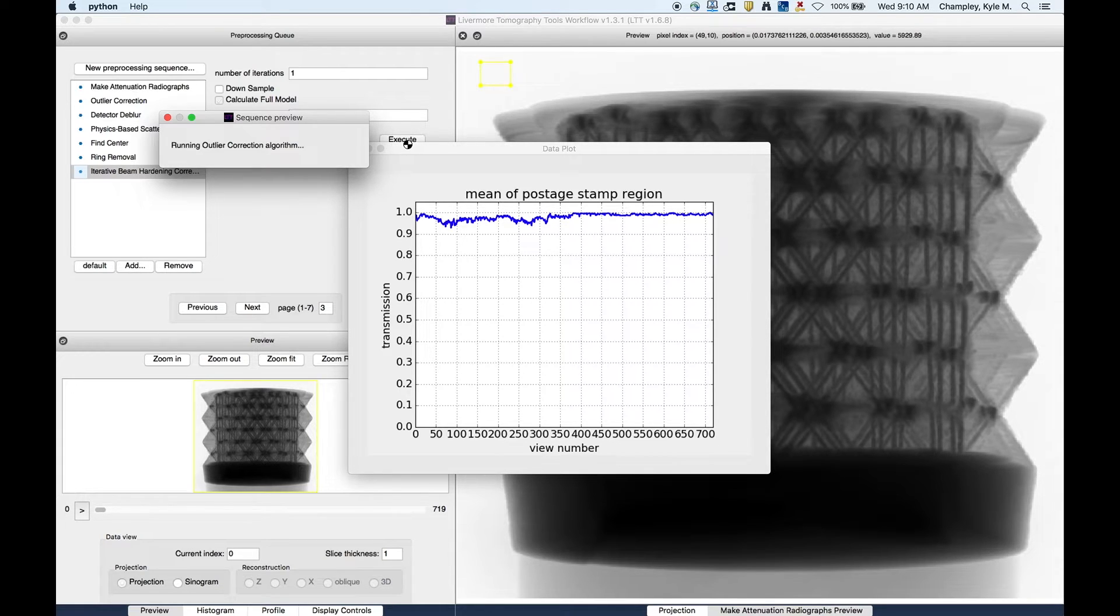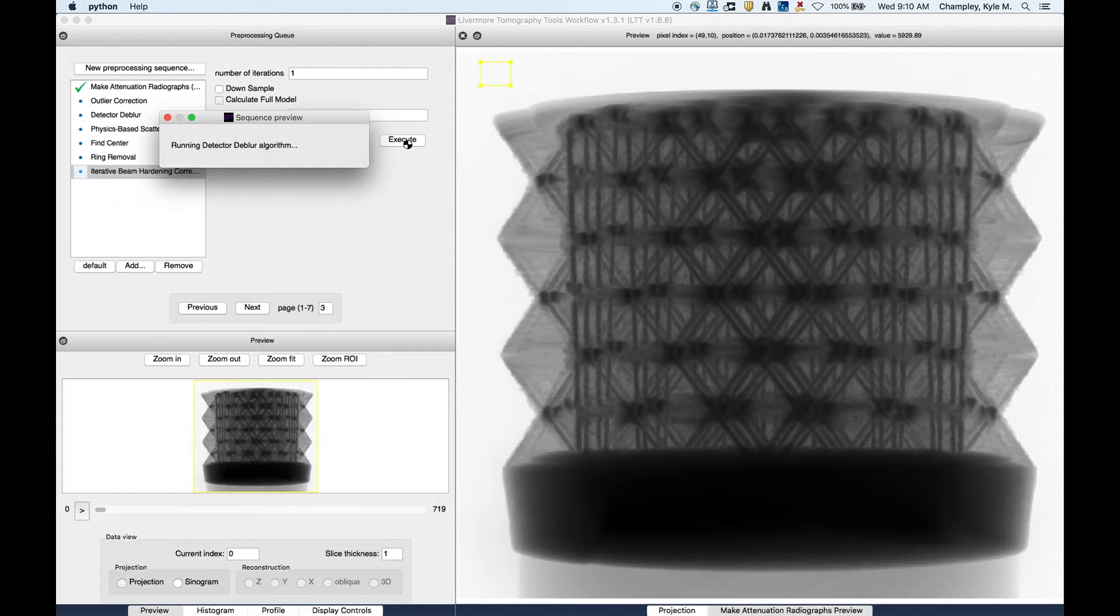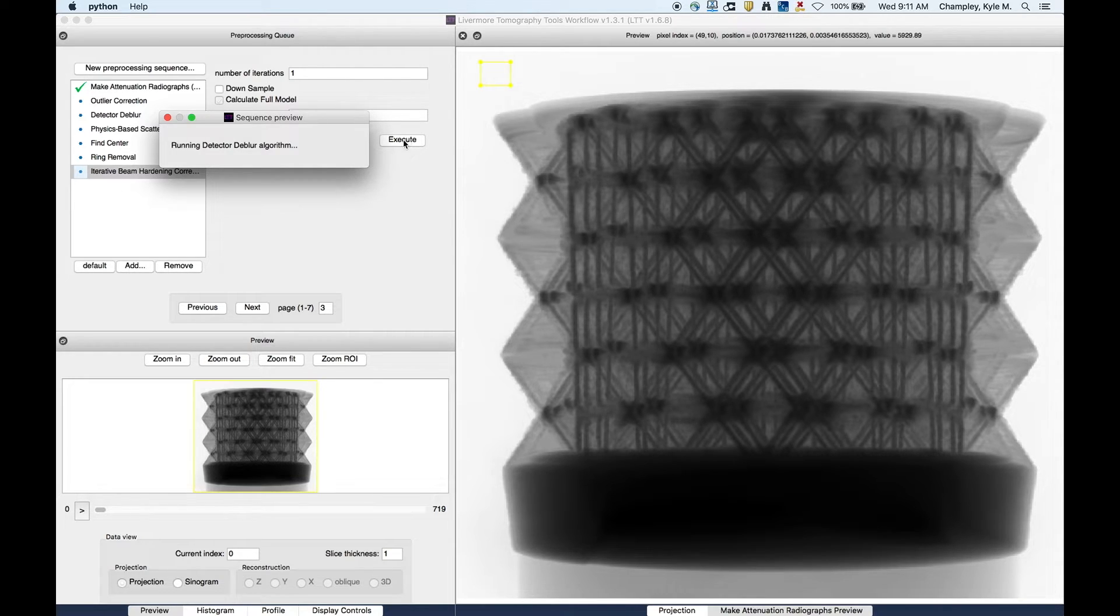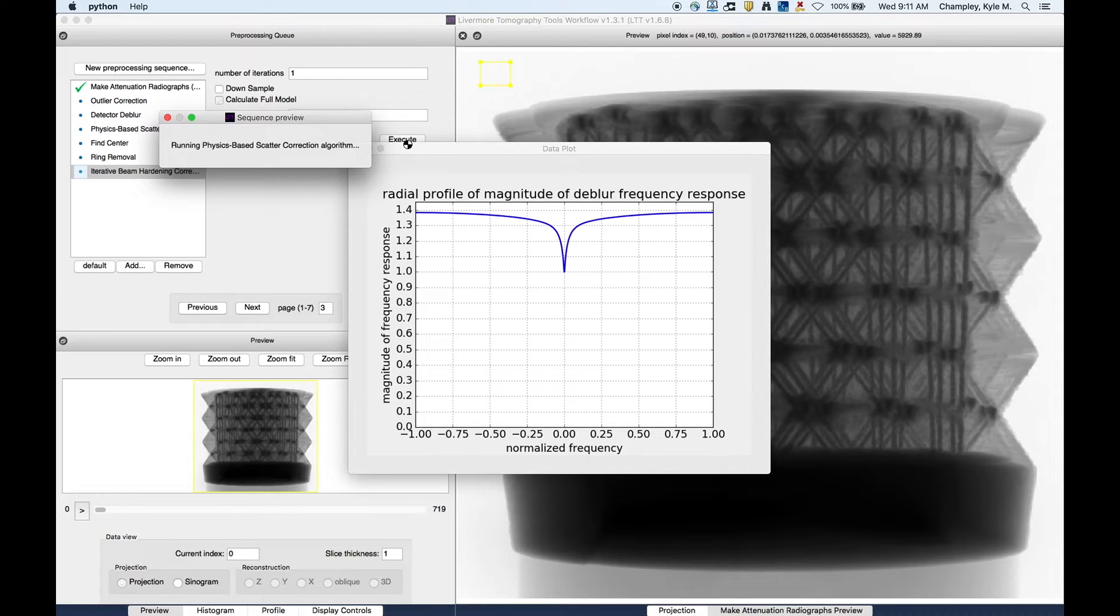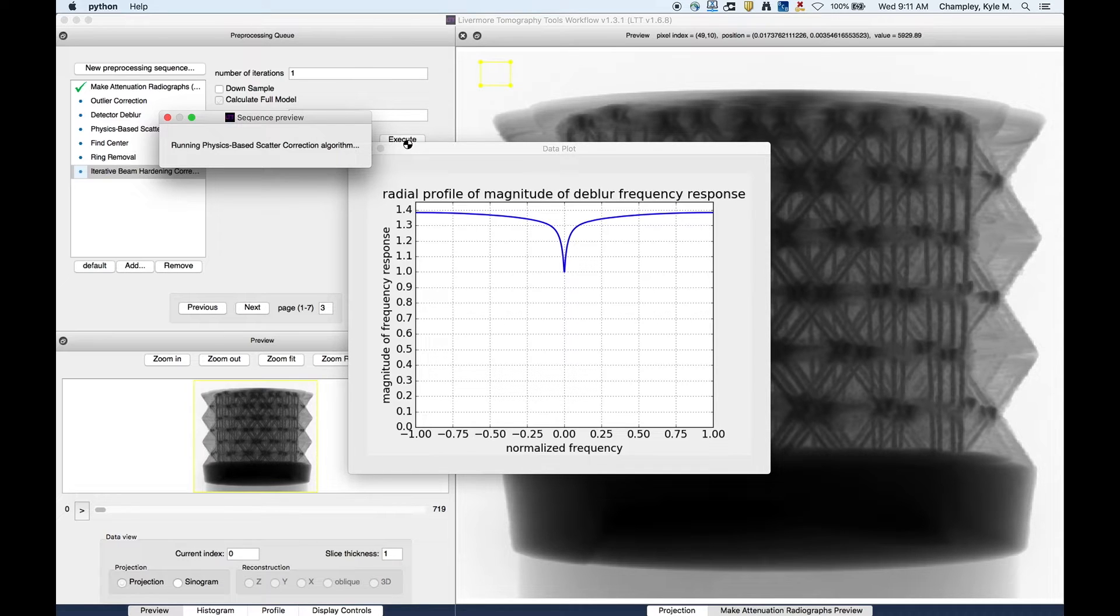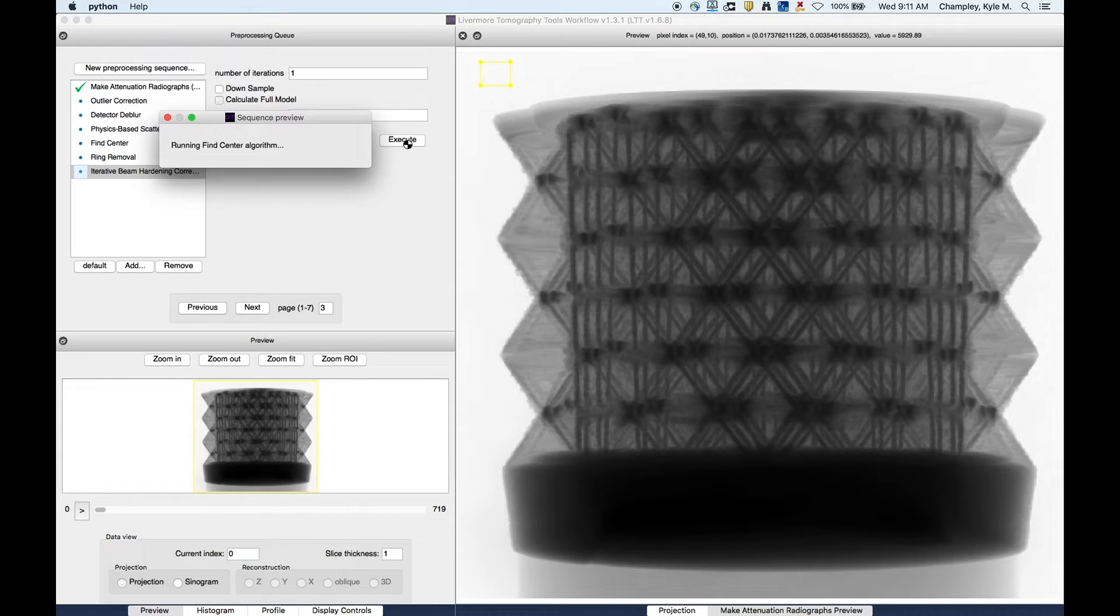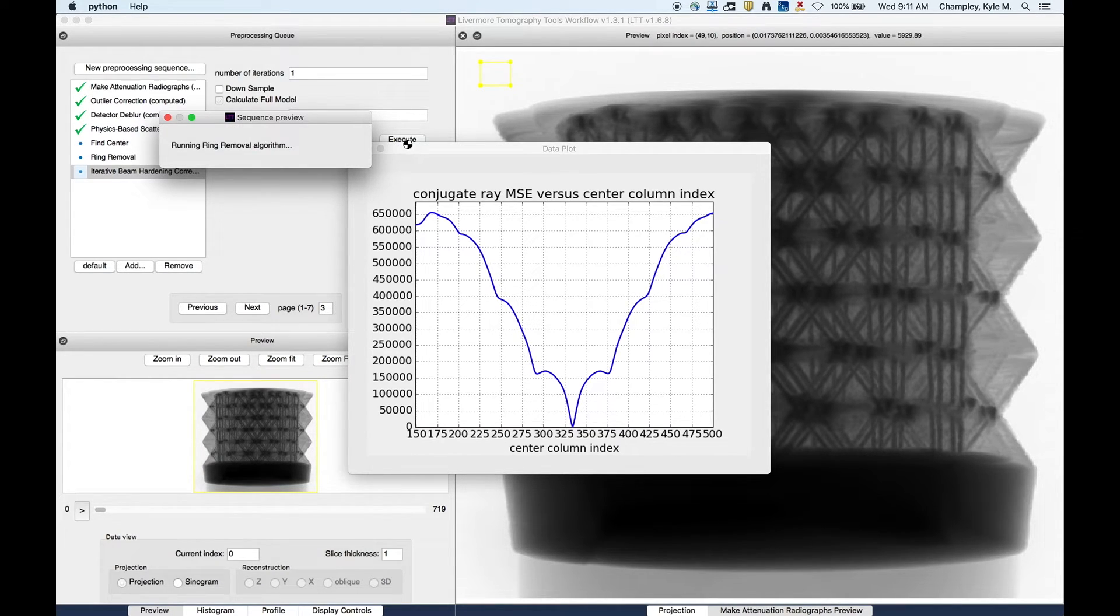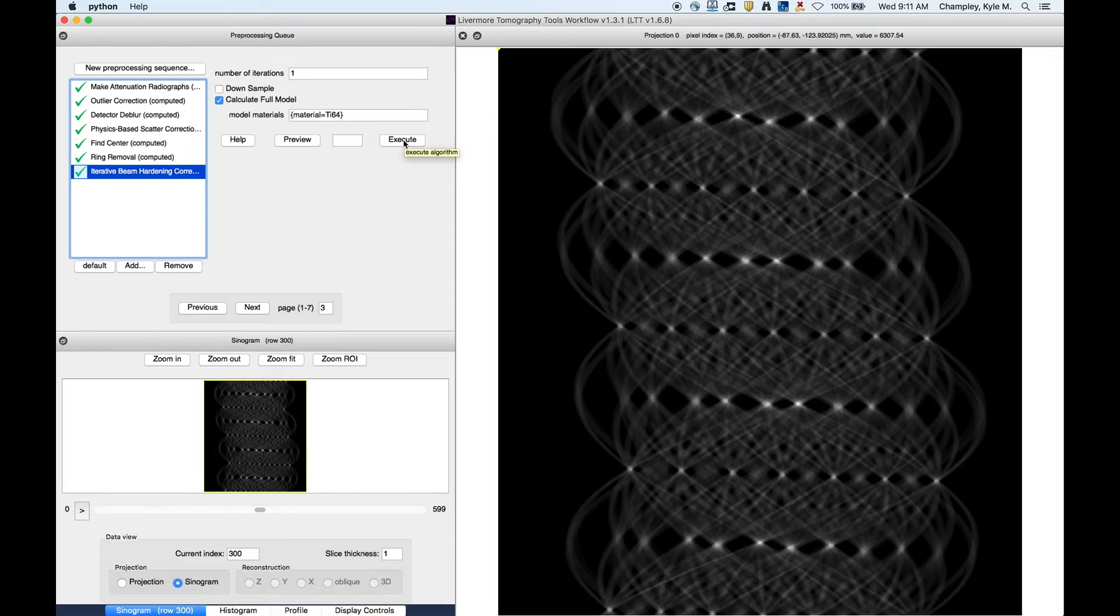Oh, so maybe the physics-based correction. So the physics-based scatter correction. So the way it works is it takes your radiograph and it down-samples it because the scatter signal is usually a low-frequency signal. And then it estimates first-order scatter from that. And then for the second-order scatter, it kicks off like a really dumbed-down Monte Carlo simulation to do the multiple scatters. And that one assumes it sort of simplifies the geometry a little bit more. And the higher-order scatter assumes that it's one single value that you're trying to estimate. So it's flat for higher-order scatter. Anyway, I guess that wasn't so long. So it's done now.